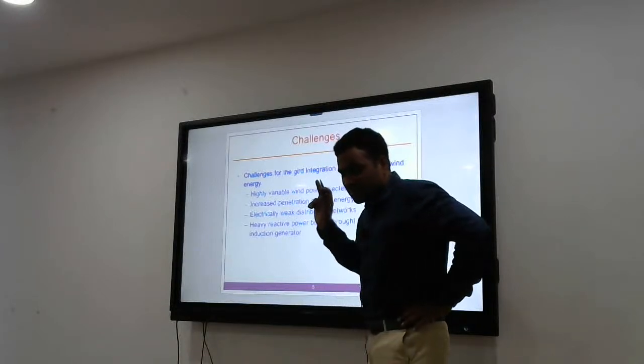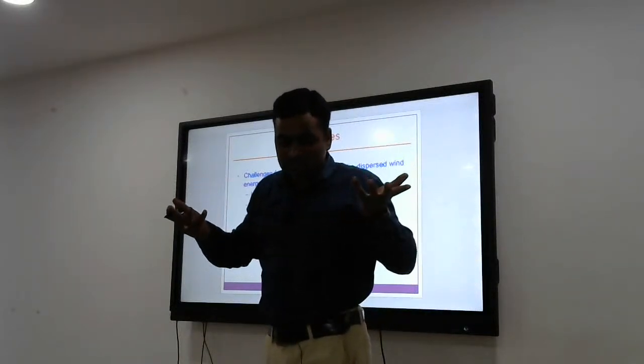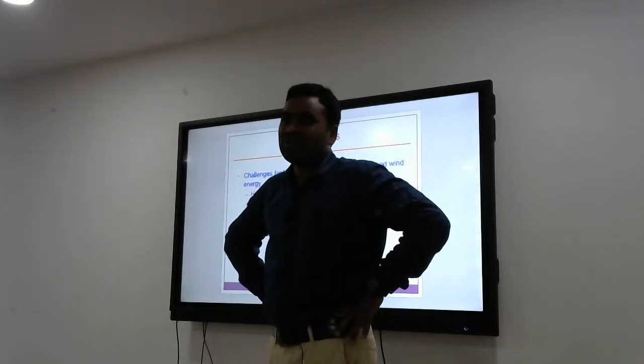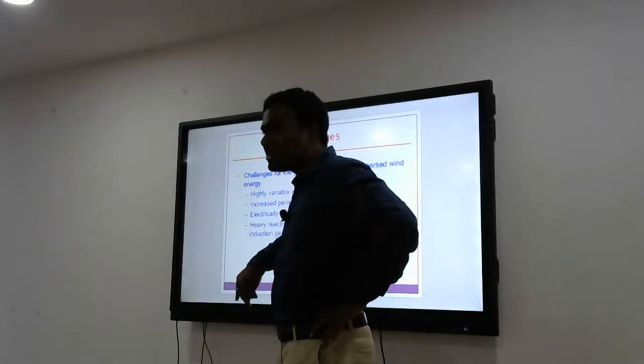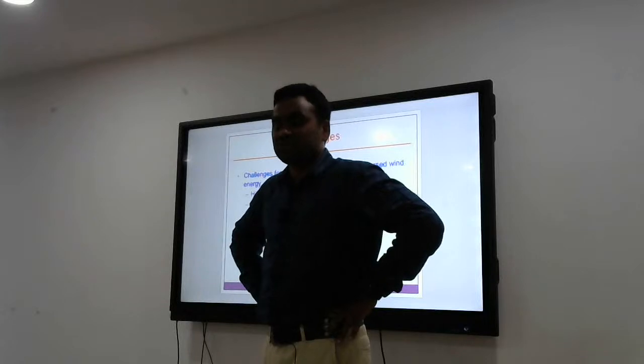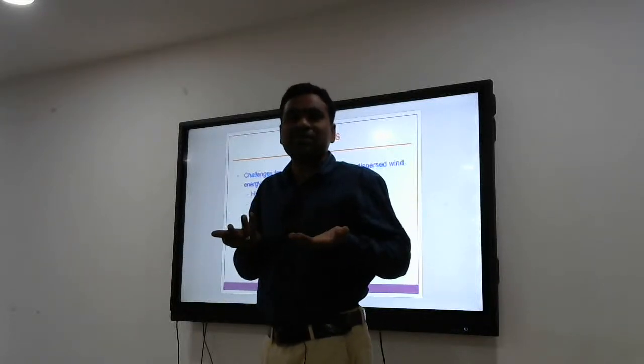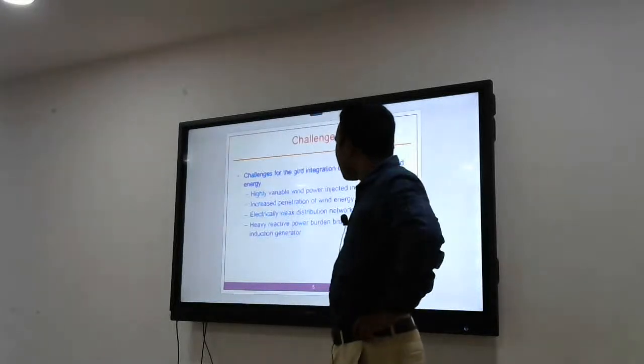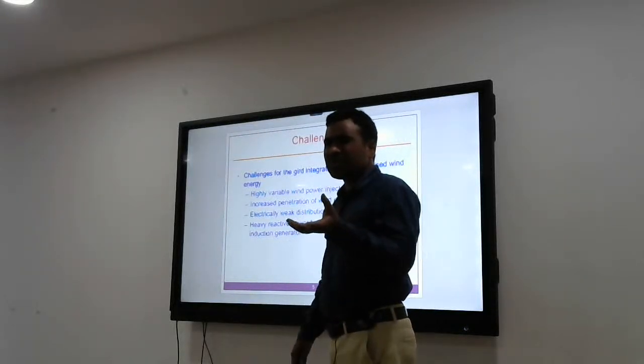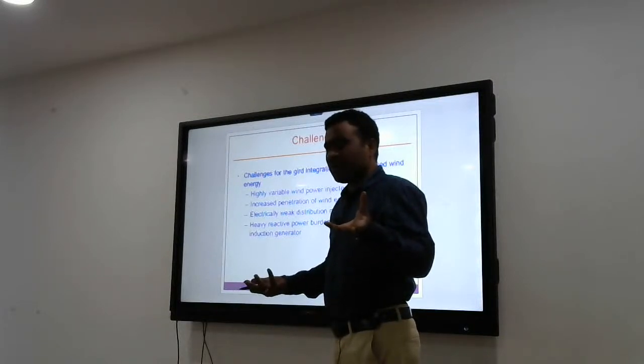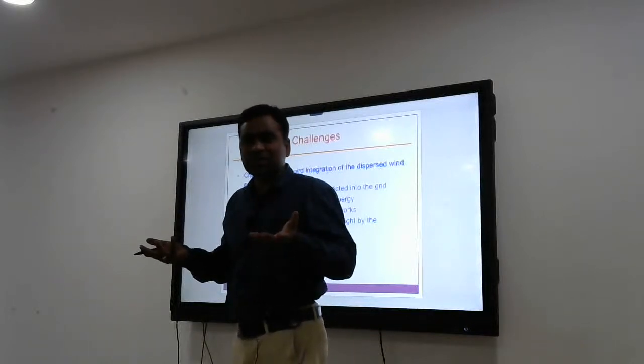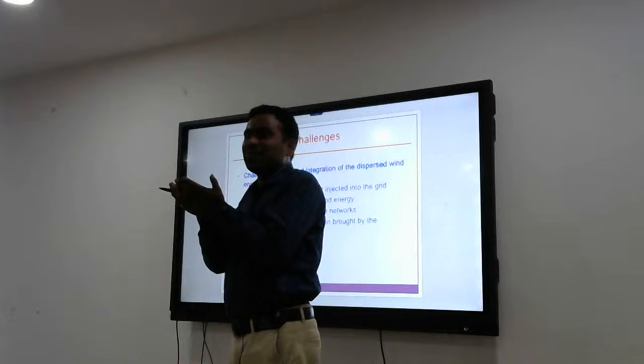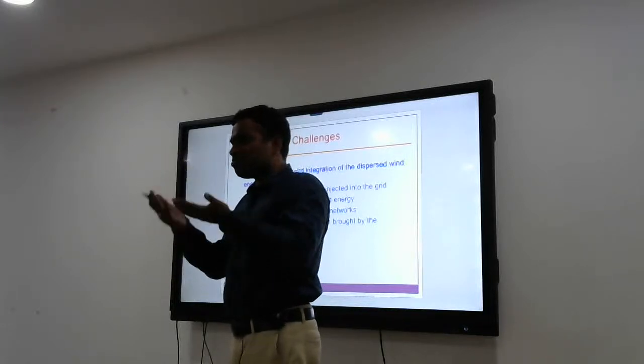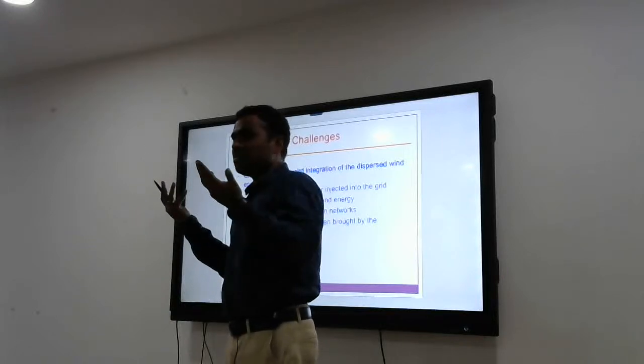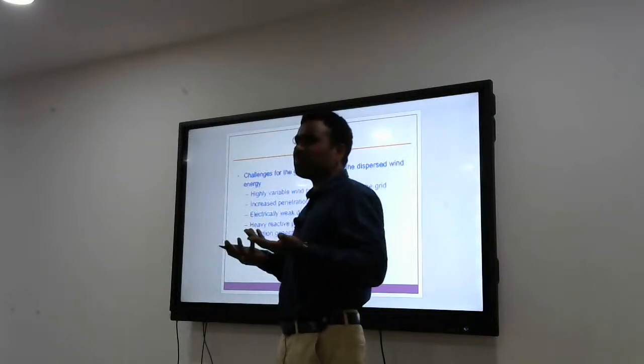The other is increased penetration of wind energy. Here the problem is, suppose wind energy penetration has increased, out of the total installed capacity of Indian power generation. We don't know when you will have more wind, when you will have less, but you have to give power to the consumers always. Due to this variable nature of wind, the problem is, now we have around 5%, 6%, I think even less than 4% of wind in the total installed capacity. Suppose that has increased to 15%, or total renewable has increased to more than 50%, then you never know when, suppose solar is there, wind is not there, or solar is not there, you can't guarantee the power. That's the problem.